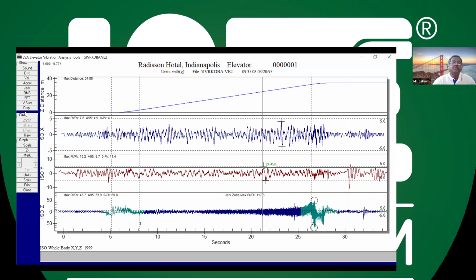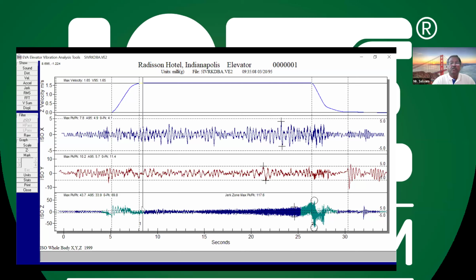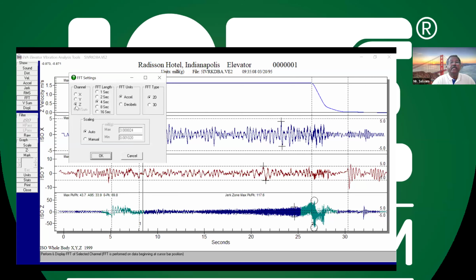So the FFT method, fast Fourier transform, means you are going to identify the different frequencies in a vibration, and which frequency is causing the maximum problem. I'll do it for a particular one. See, this is the velocity curve. Here, for example, we are taking this high speed point, at the end of acceleration. For a particular area we are taking it and trying to analyze. So we are doing FFT on the Z axis. We take a snapshot of 4 seconds interval and we will check.